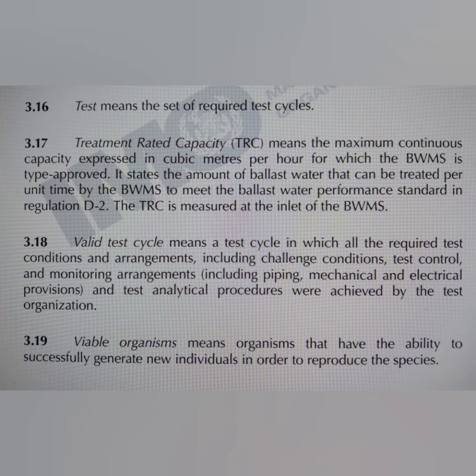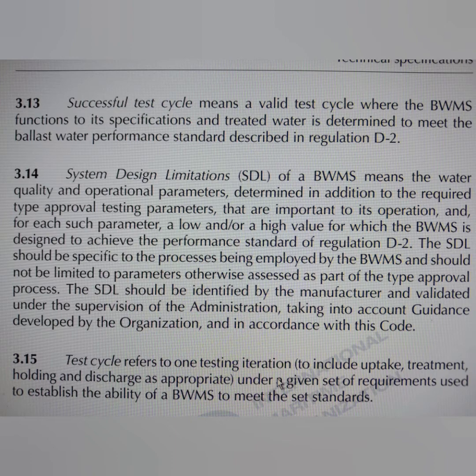I will now quickly discuss two definitions which may be important. System design limitation means the water quality and operational parameters determined in addition to the required type approval testing parameters that are important to its operation, and for each such parameter a low and/or high value for which the ballast water management system is designed to achieve the performance standard of regulation D2. Basically, in addition to what is required by D2, there are additional features, and all those features must have low and high value parameters provided by the manufacturer and identified under the supervision of the administration.